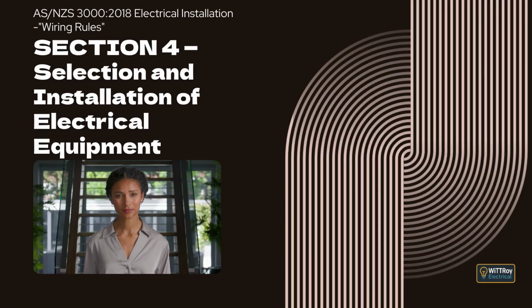Clause 4.19 Air conditioning and heat pump systems. Air conditioning and heat pump systems that incorporate a compressor must be provided with a lockable isolating switch in accordance with Clause 2.3.2.2, installed adjacent to but not on the unit, and arranged so that all parts of the system, including ancillary equipment, are isolated, with additional isolating and warning arrangements required where internal and external units are supplied separately. Clause 4.20 Lifts. Clause 4.20.1 General. Electrical installations for lifts must comply with this standard and the applicable building code, covering electric lifts, electro-hydraulic lifts, goods lifts, passenger lifts, and motor room-less lifts, with emergency lifts also meeting the additional requirements for safety services.